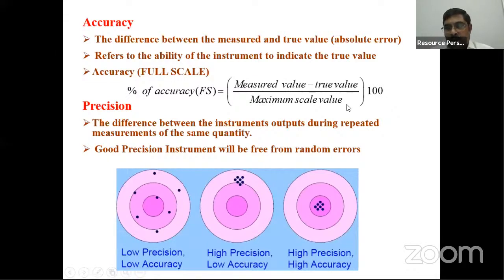For example, take a pressure sensor. The difference between the measured value and the actual value, let's say pi, in Pascal, and the maximum scale value is 1000 Pascal. So pi divided by 1000 multiplied by 100 gives the accuracy. This is usually expressed as plus or minus some percentage.